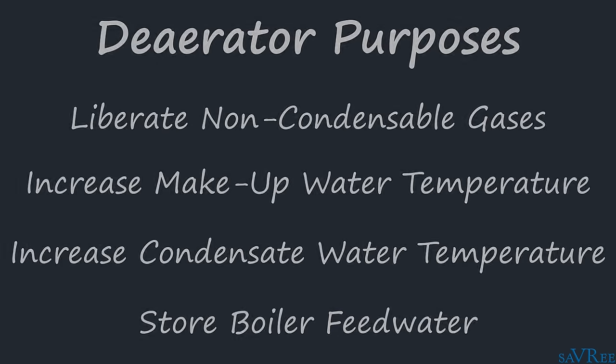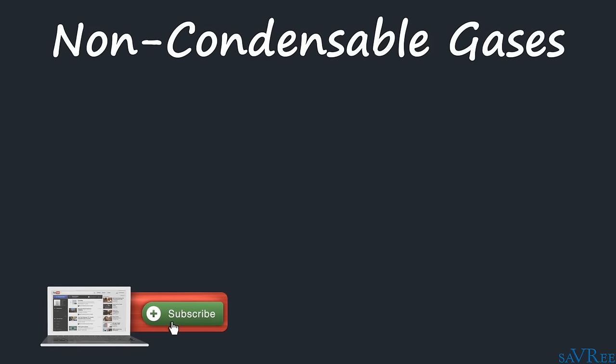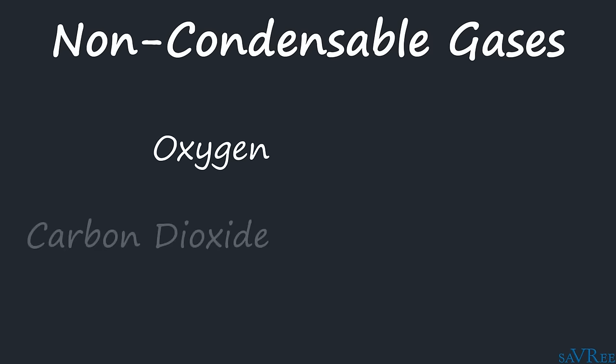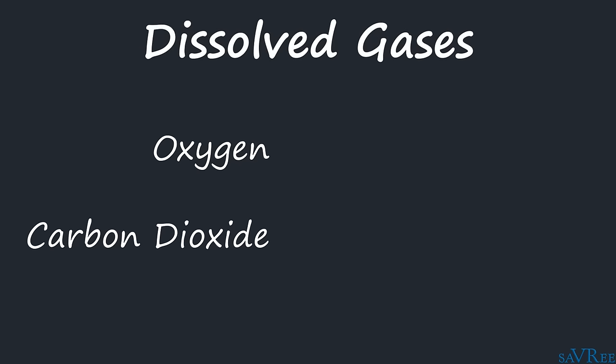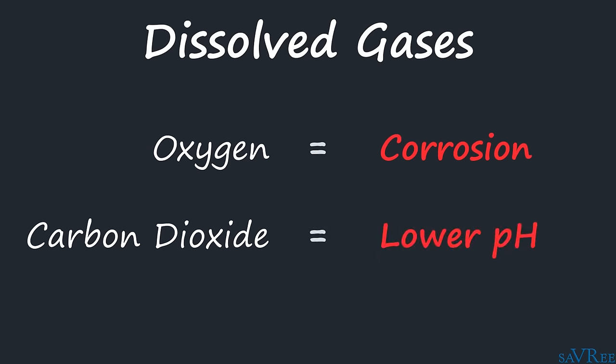When we're talking about non-condensable gases, the two gases we're most interested in are oxygen and carbon dioxide, also referred to as CO2. These non-condensable gases are present in the boiler feed water and are referred to as dissolved gases because they are dissolved into the water. The problem with having oxygen in the boiler feed water is that it can lead to corrosion. The problem with having carbon dioxide in the feed water is that it makes the water more acidic. A typical boiler will use feed water with a pH value of between eight to eleven, so if we have excess CO2, we're going to have feed water with a lower pH.